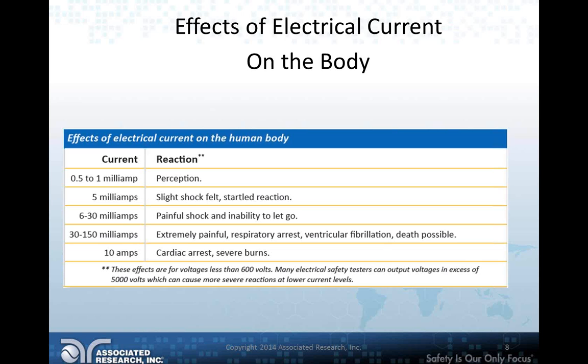But in the 30 to 150 milliamp range, this is extremely painful electrical shock. This is when you can go into ventricular fibrillation, respiratory arrest, and death is possible in this range. And then, of course, if we jump up past this, to 1 amp, 10 amps, whatever, you're talking about severe third-degree burns and cardiac arrest. So death is almost certain when we're talking about this range in these voltages of about the under 600-volt range.